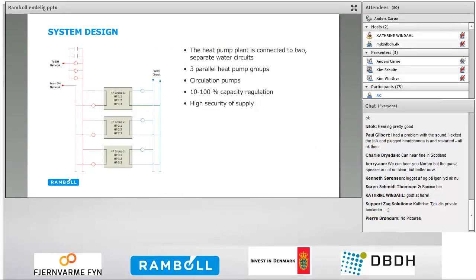Looking at the overall system design, the plant is connected to 2 separate closed-loop water circuits. On the right-hand side here, the heat pump plant is connected to the waste heat recovery circuit, where the heat pumps produce chilled water that is distributed to Facebook through large underground pipes. At Facebook, the water runs through chilled water coils that cool down the hot air from the servers, and this process then heats up the chilled water before it's returned back to the heat pump plants.